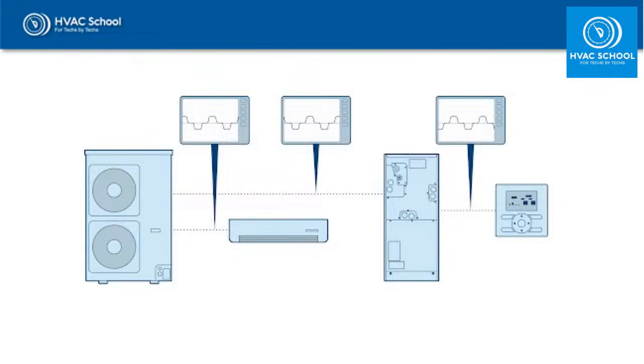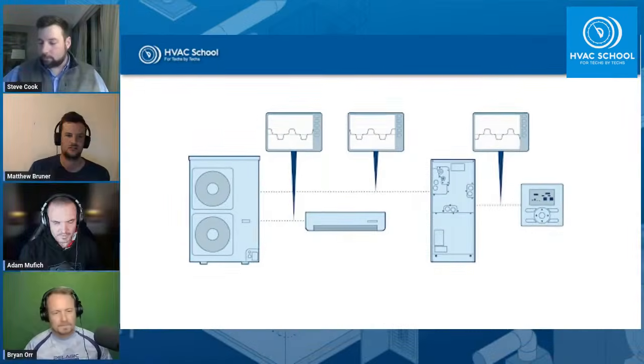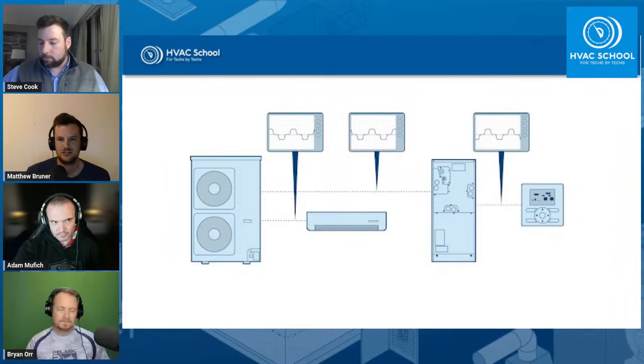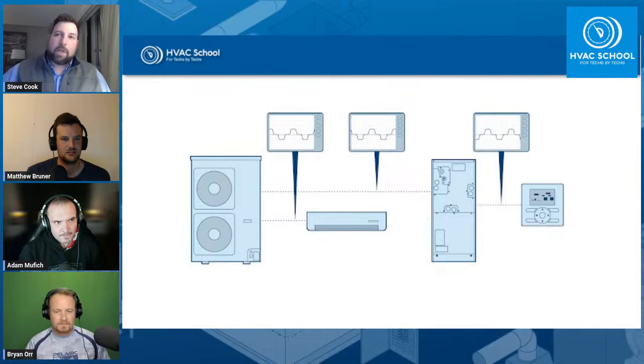Steve, I wanted to back up a second. A little earlier, you were saying that the indoor unit and the outdoor unit kind of talk and listen back and forth. Does that mean that whatever protocol is being used, you'll be sending voltage from the indoor unit to the outdoor unit and vice versa? Can you read voltage both directions? You really can't read voltage both directions. What it's doing, yes, it will send a voltage signal, but it'll be going too fast for a meter to pick it up, and it will be less than what you're actually going to read.